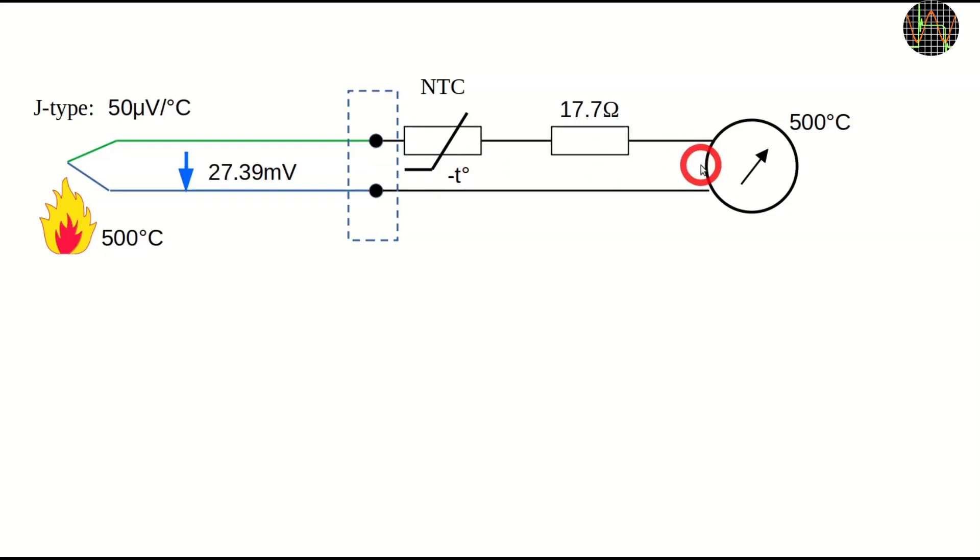But now, the NTC in series with the instrument lowers its resistance the warmer it gets, thus less voltage is dropped over the NTC and this raises the instrument readout. If done properly, the resistance dropped by the NTC compensates exactly for the increase in negative voltage at the cold junction at ambient temperature.